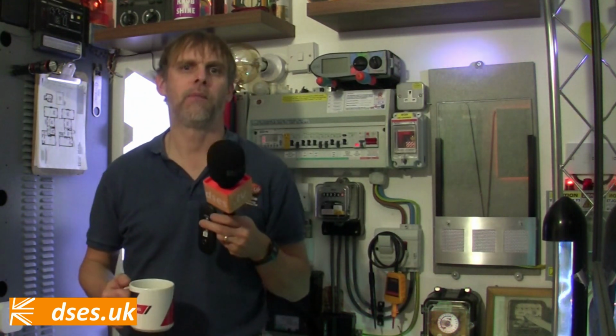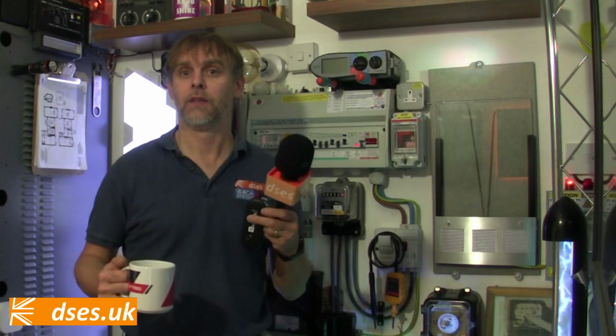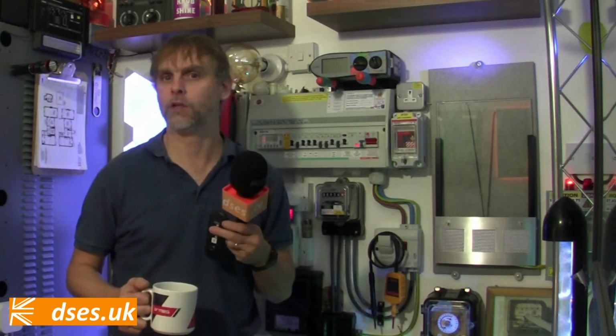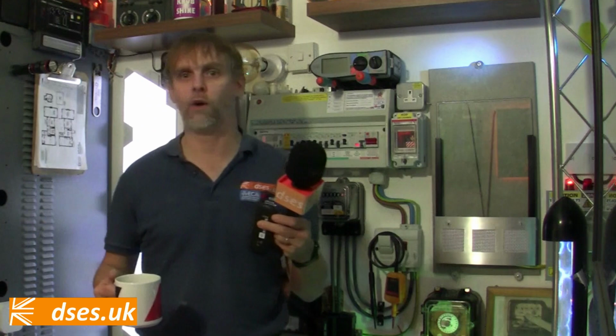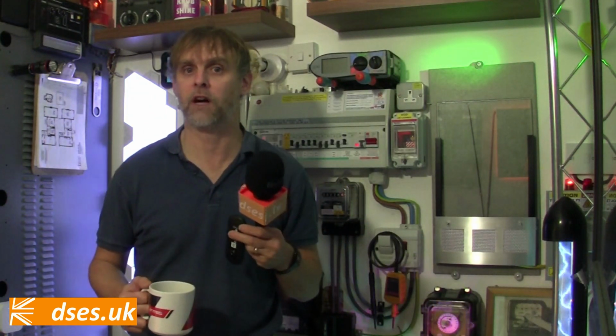AFDDs and metal enclosures are a shoulder shrug to say, let's try to stop the fire from a loose connection when it starts, rather than there being an industry shake-up to put the clueless or the cowboys out of action. Stop coming up with new ideas on how to contain the disaster when it happens and do something to raise the bar. This is yet another cure over prevention. If the aim is to cut down on electrical fires, start by mandating EICRs and properly accrediting who should be doing them. Make it a clause of standard home insurance that payouts for electrical fires, shock injury or failed equipment are perhaps at risk if you can't prove the electrical installation is properly maintained. Maybe lower premiums for those who can produce bona fide paperwork.